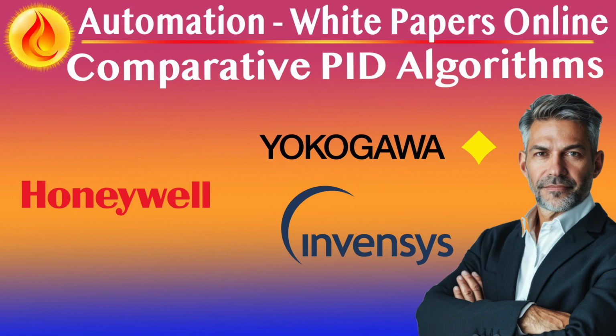Invensys Foxboro, in contrast, traditionally uses a series algorithm, especially in legacy IA series systems. This format is historically rooted in pneumatic electronic control logic and introduces interactions between derivative and integral terms. These interactions change the effective behavior of P, I, and D terms depending on their relative values, making tuning less straightforward without conversion knowledge. Modern Invensys systems also support ideal algorithms in newer EcoStruxure and Foxboro Evo environments, but series forms are still widely used in existing infrastructure.